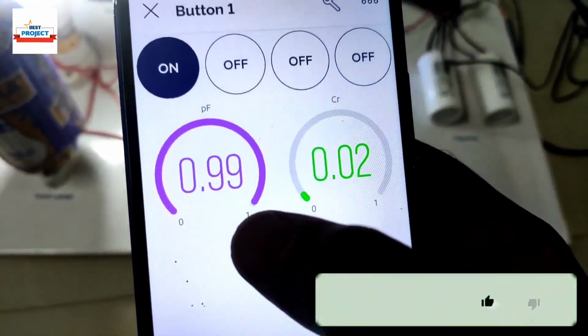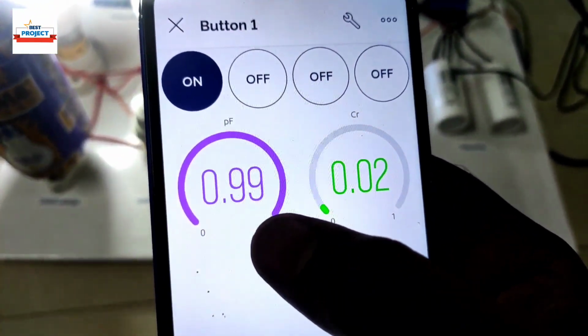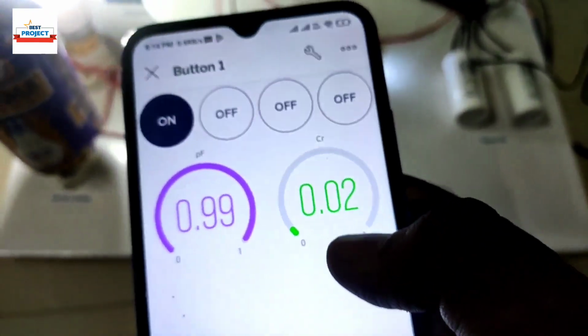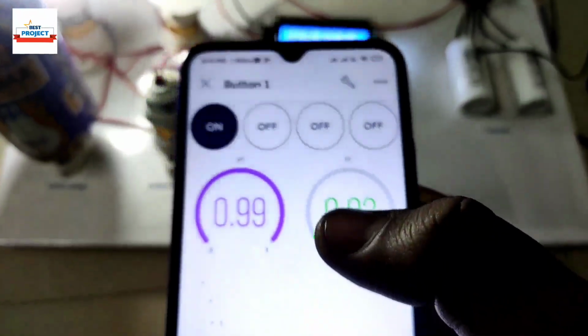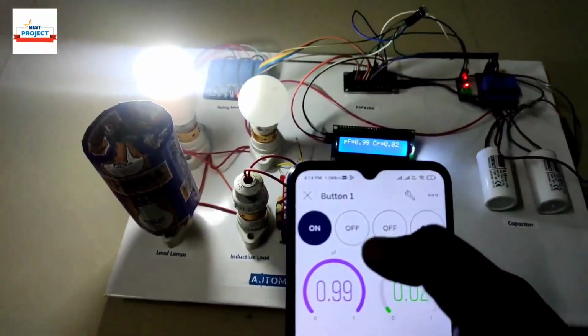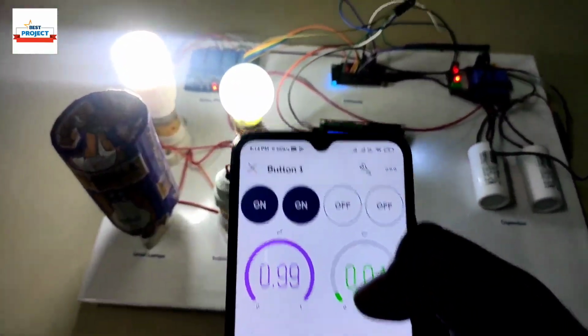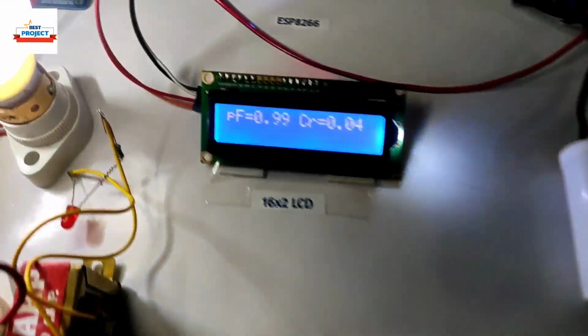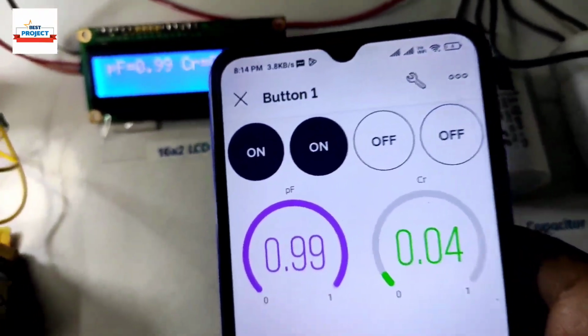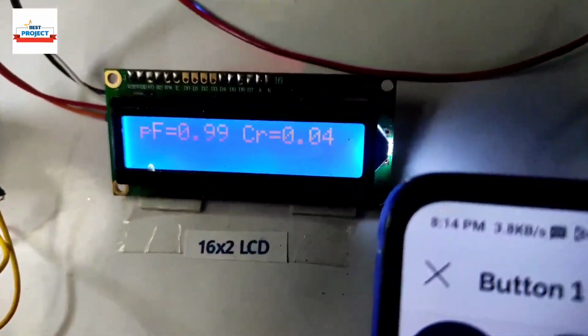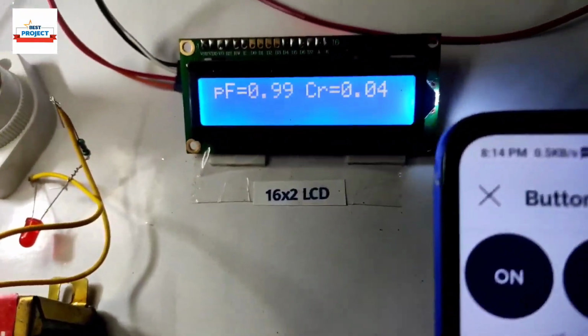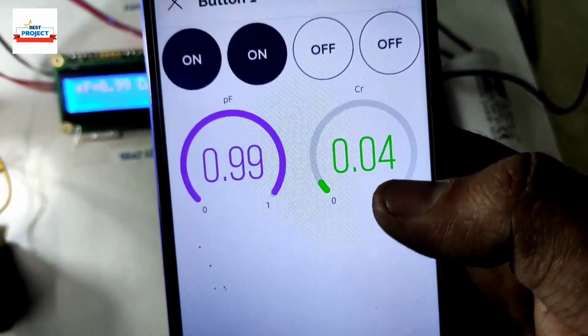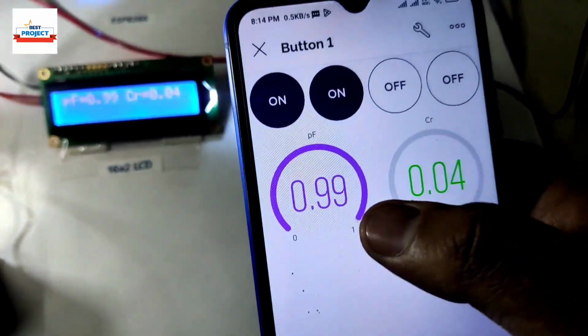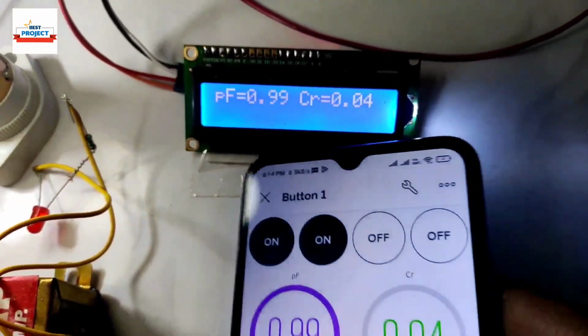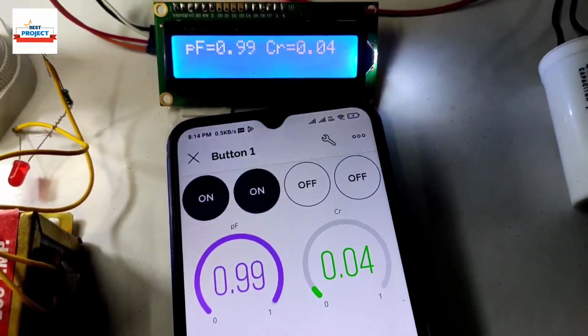So you can see the first load has turned on, and the power factor is currently still 0.99, and the power factor was corrected by 0.02 only. Okay, let's turn on the second load. See, the second load has turned on here. You can see all the data on the LCD as well as on the app. So you can see the power factor is corrected to 0.99, and the power factor correction value was 0.04. You can see the same on the app and on the screen.